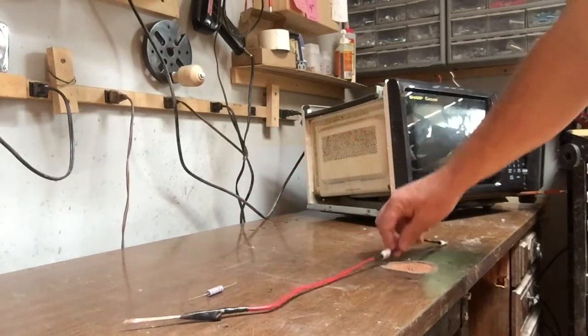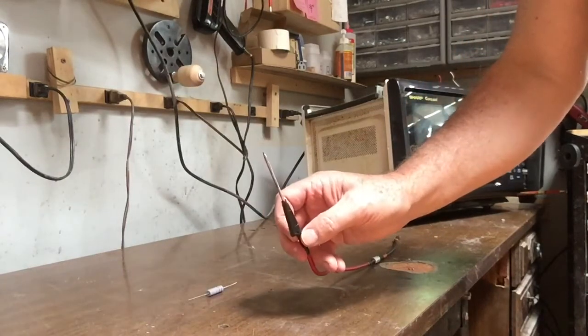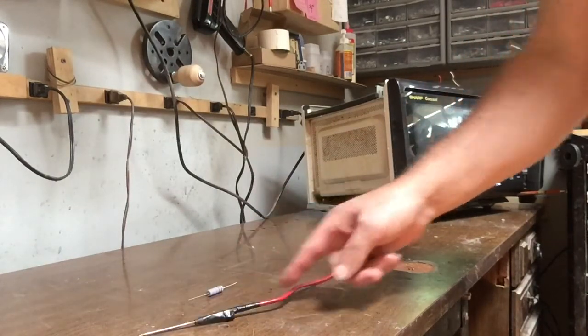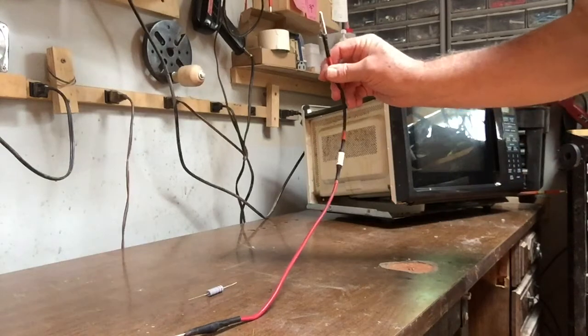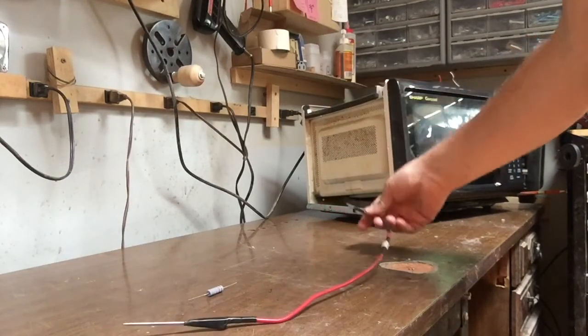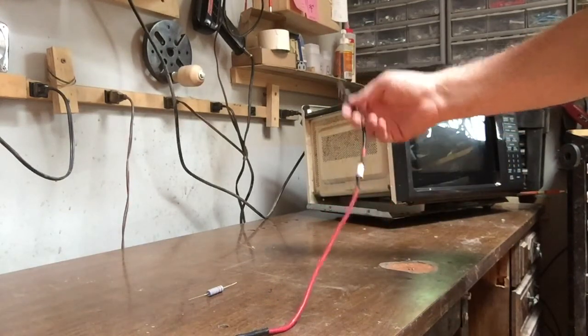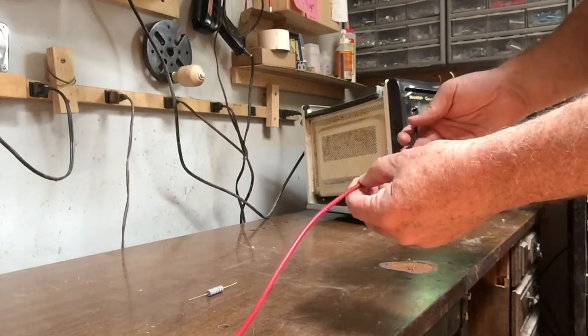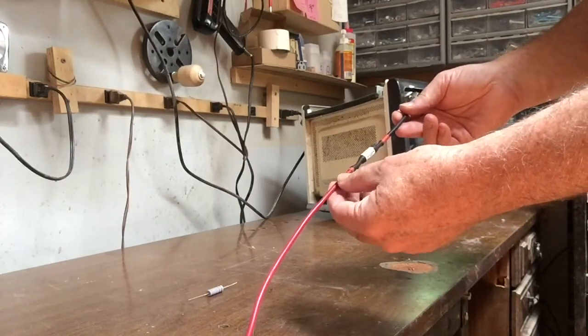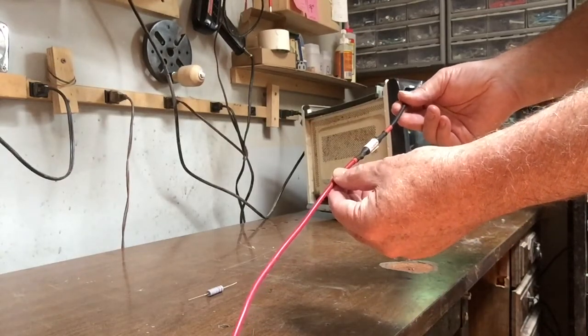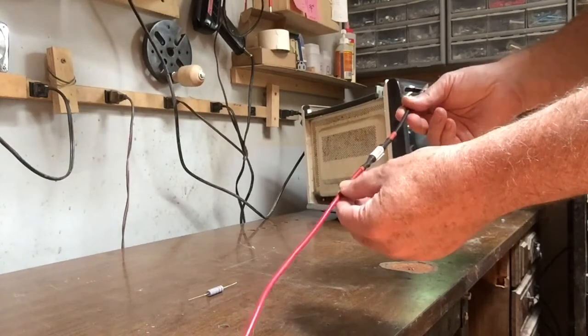So you simply just take a wire. In this case, I took a wire and put a nail on one end, sharpened it so I can use it as a probe. It's insulated, with an alligator clip to ground on the other side, and a little bit of shrink wrap insulation on that. In the middle of it, I put a 20 kilohm resistor, and that will allow the capacitor to discharge without creating a spark.